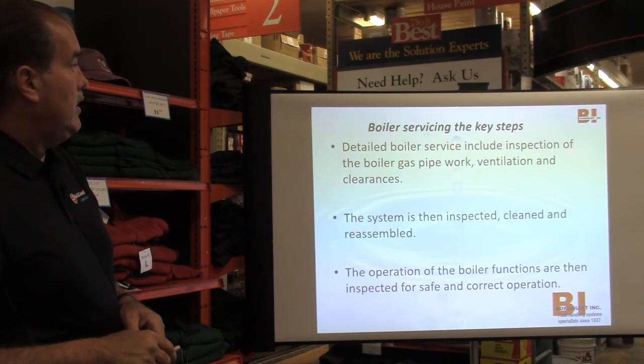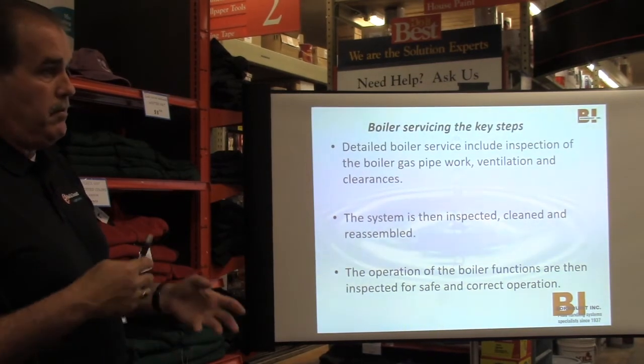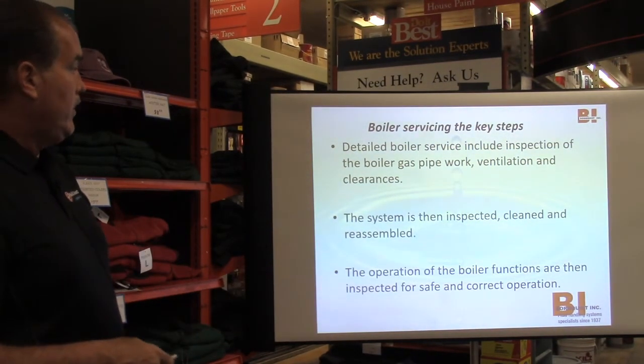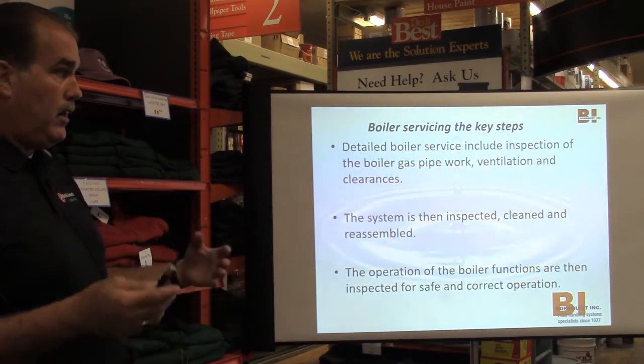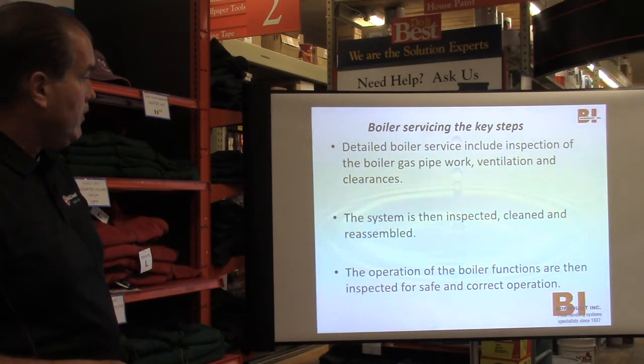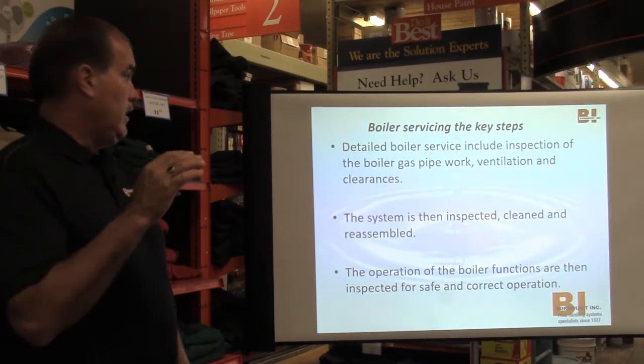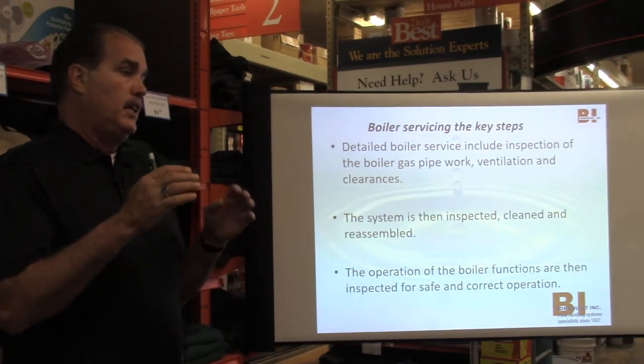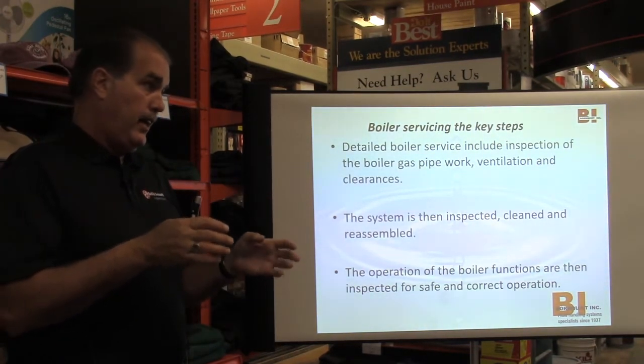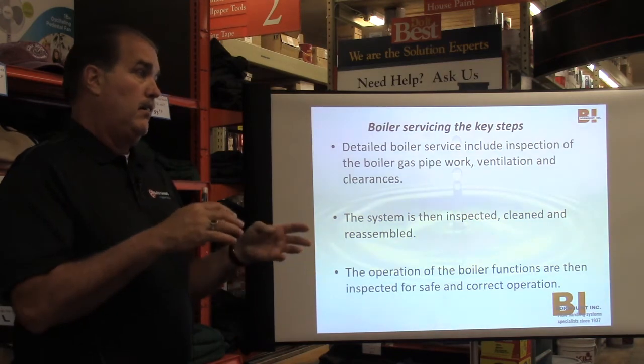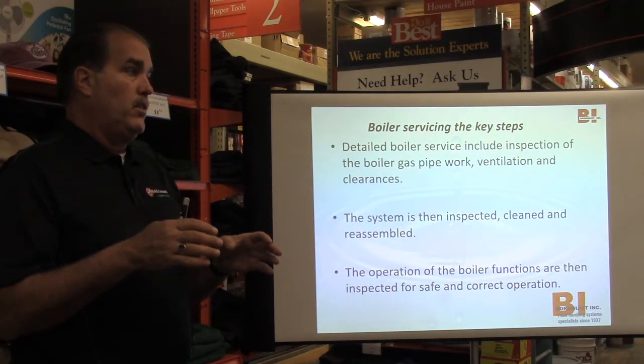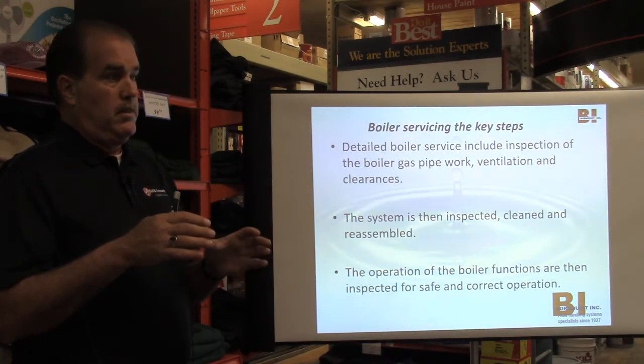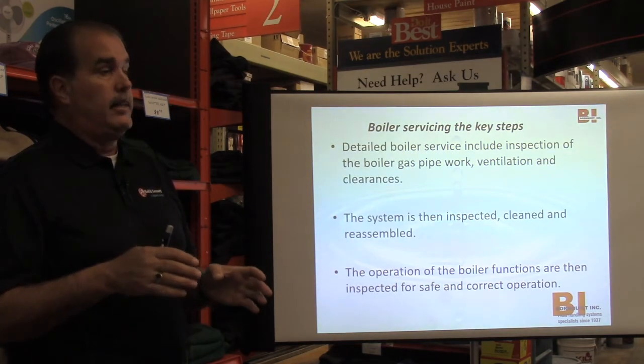But besides that, he should be inspecting the gas piping, making sure that's fine. The ventilation, the stuff around the boiler, not only inside the boiler. They should inspect and clean the heat exchanger, inside and out.